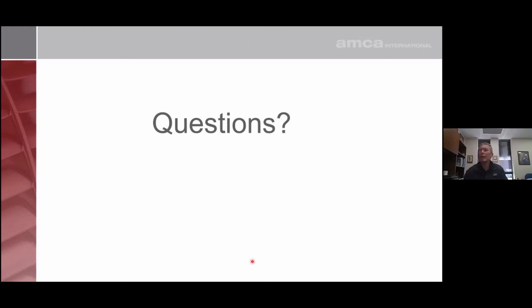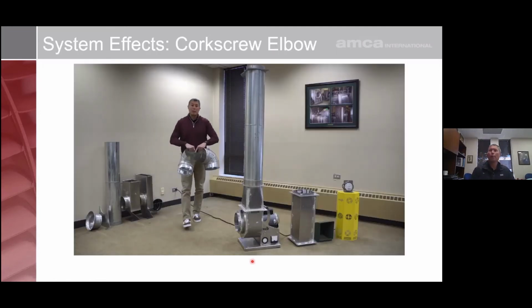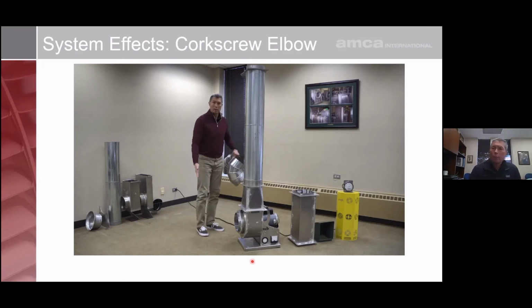Okay, any questions on an inlet valve or inlet or an elbow with a turning vane at the inlet of the fan? Okay, we'll move on to the next section, which is corkscrews. Now, we've oftentimes seen installations of fans where you have a wall here, and so you don't have a whole lot of space in order to run ductwork into the fan. And what we're going to do is create a corkscrew and see how corkscrews affect the fan's performance.